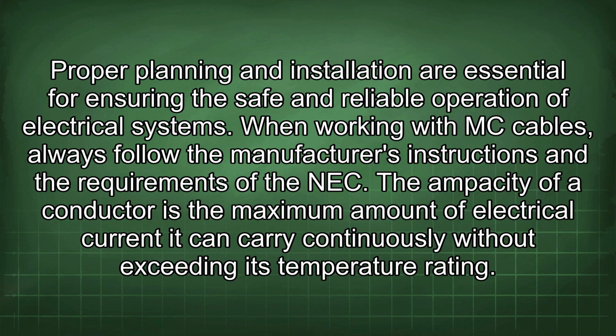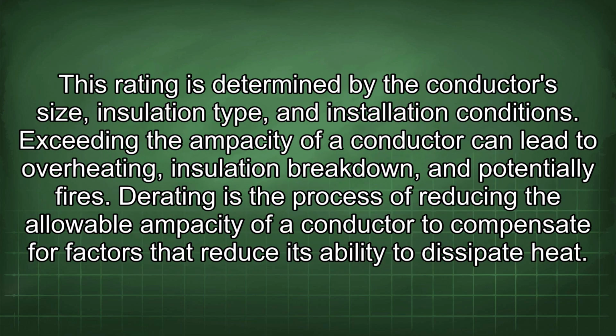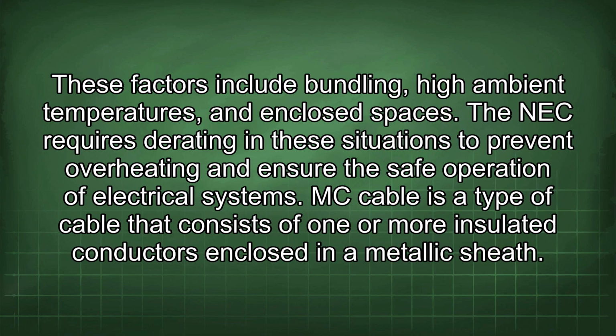The ampacity of a conductor is the maximum amount of electrical current it can carry continuously without exceeding its temperature rating. This rating is determined by the conductor size, insulation type, and installation conditions. Exceeding the ampacity of a conductor can lead to overheating, insulation breakdown, and potentially fires. Derating is the process of reducing the allowable ampacity of a conductor to compensate for factors that reduce its ability to dissipate heat. These factors include bundling, high ambient temperatures, and enclosed spaces. The NEC requires derating in these situations to prevent overheating and ensure the safe operation of electrical systems.